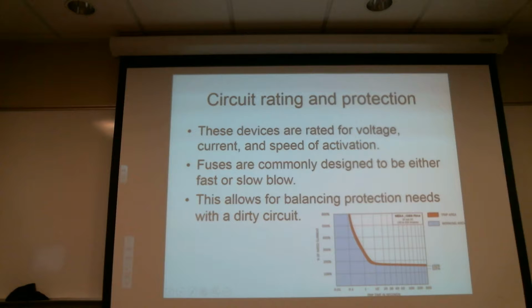Where that's needed. In most cases, the downside of a high speed acting device is any very short-term transient that gets through is enough to trip it. That is enough to blow it, right? And in most circuits, a short-term transient of current or voltage, when I say short-term, 10 or 20 or 30 milliseconds, it's not ever going to be long enough to cause the circuit to get warm. It takes a while for those wires to heat up. Unless it's serious, you know, it's a lightning bolt or whatever. And if it's really, really serious in terms of voltage and current, your circuit protection may not matter. It may be able to just blow right through it.